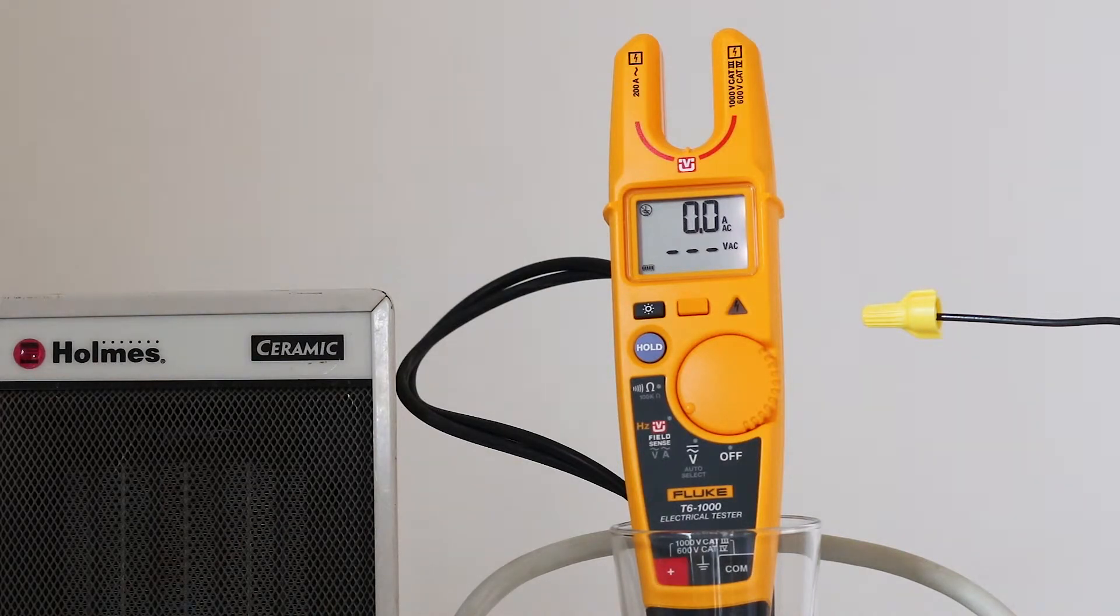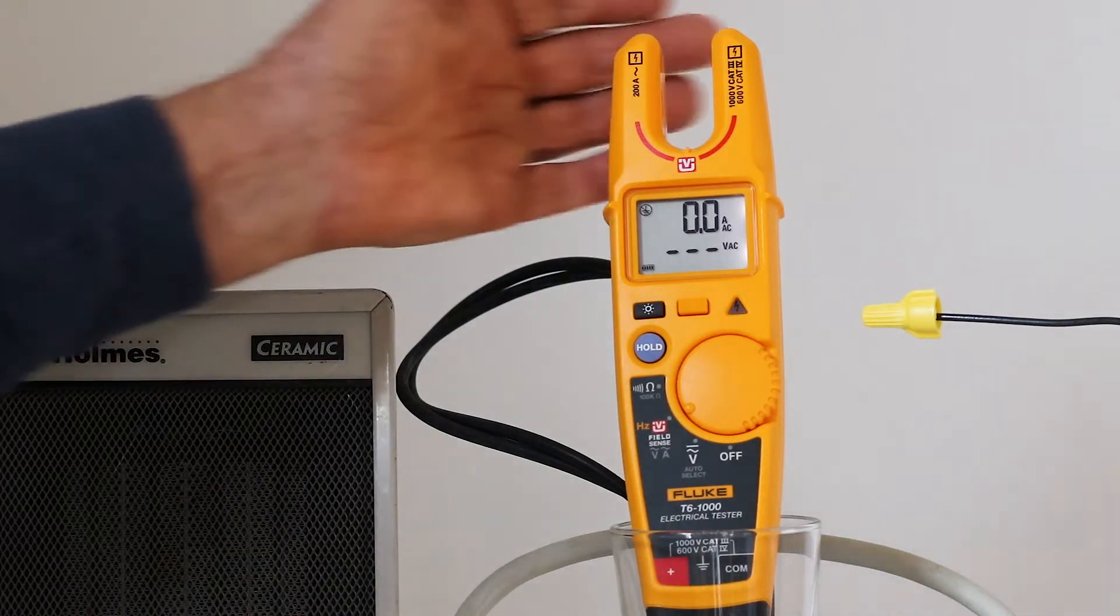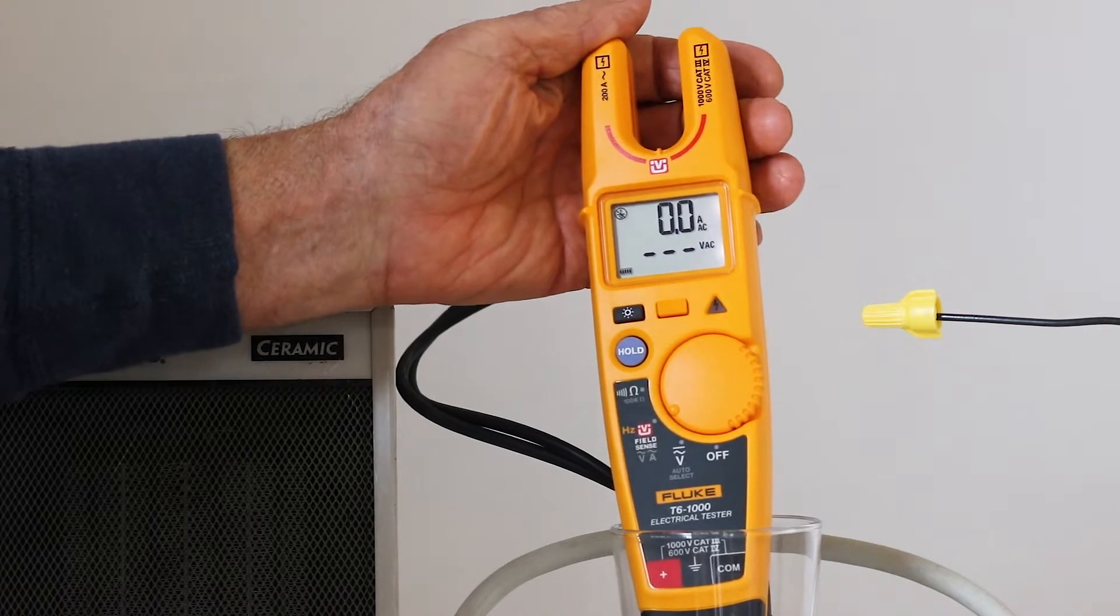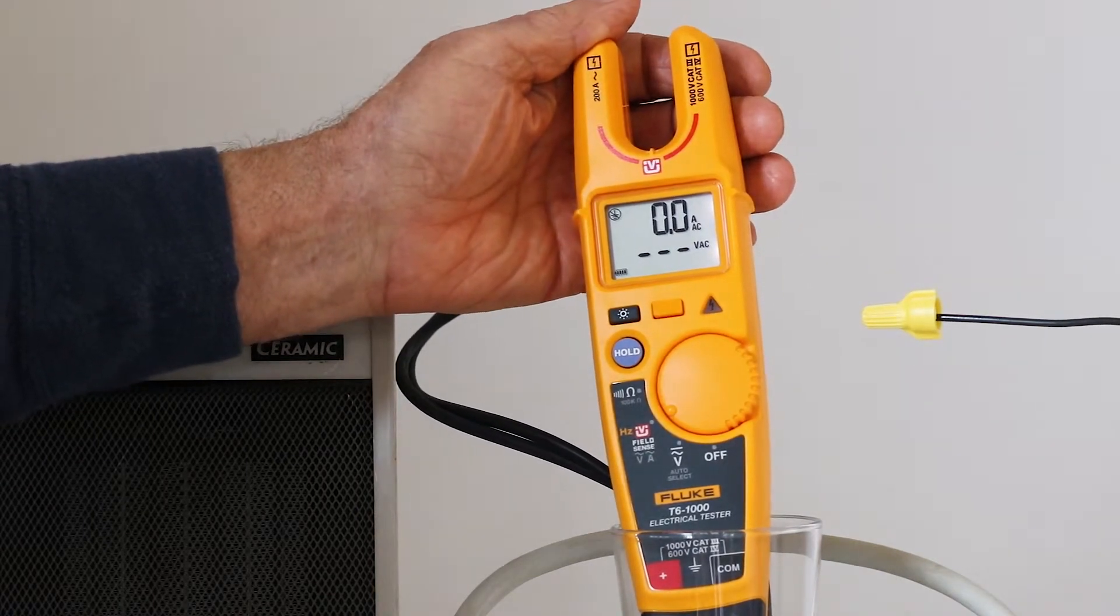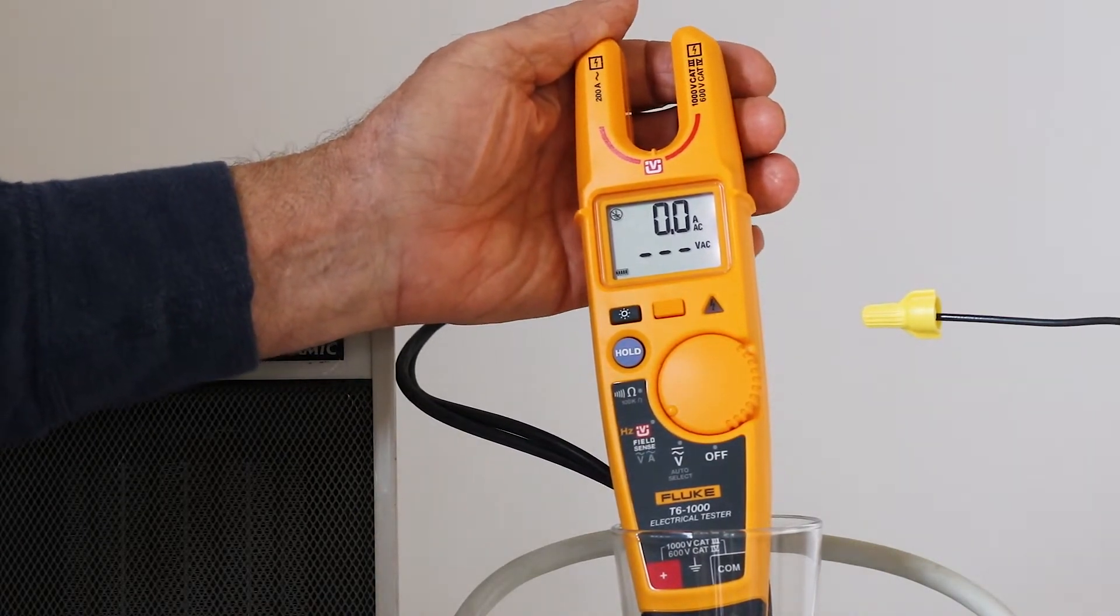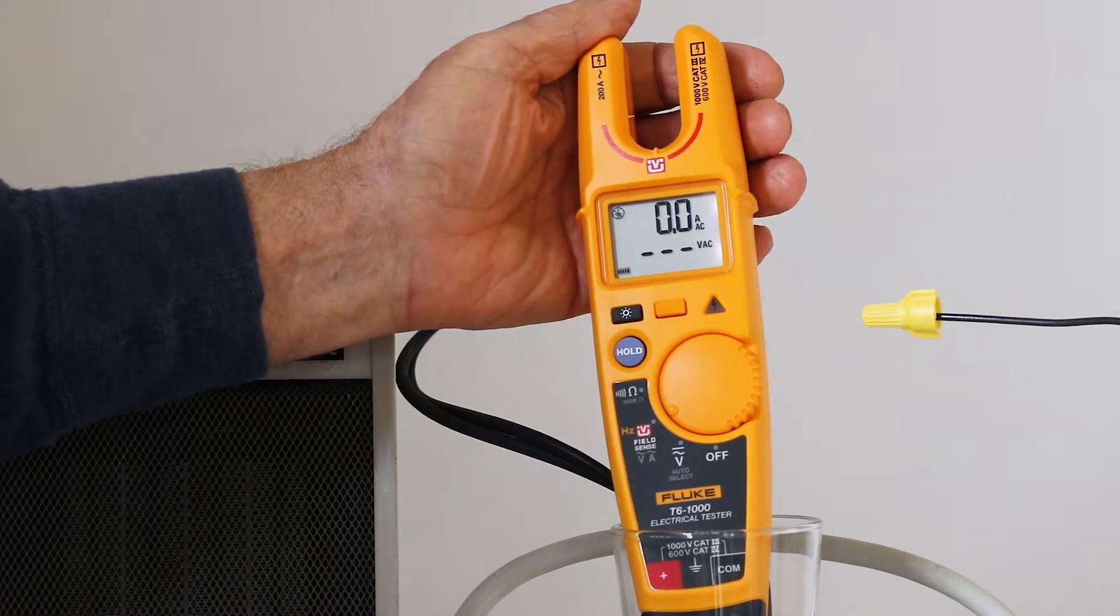This means that it is suitable for three-phase 480 volt work, including the 678 volt DC bus that we see in variable frequency drives for high horsepower motors. The open fork design means that it will accommodate a 4-aught conductor, as used in a 200-amp electrical service.